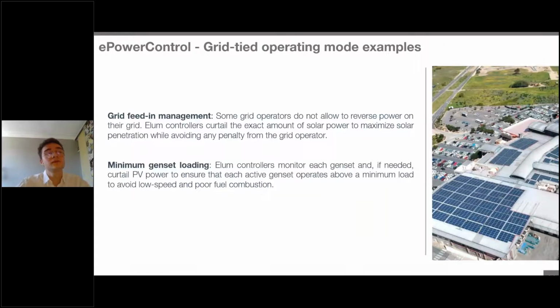So what are the different features of this e-power control unit that is installed on site and that manages the system both during grid-tied and off-grid times? Basically, when we are connected to the grid, the e-power control will be managing the power output of the inverters live to ensure that there is always this grid feed-in management.